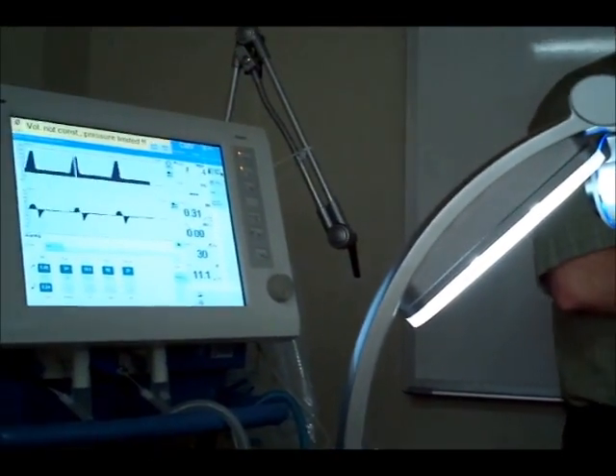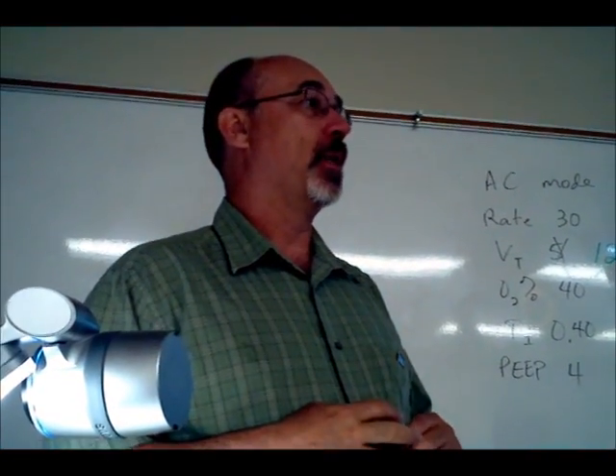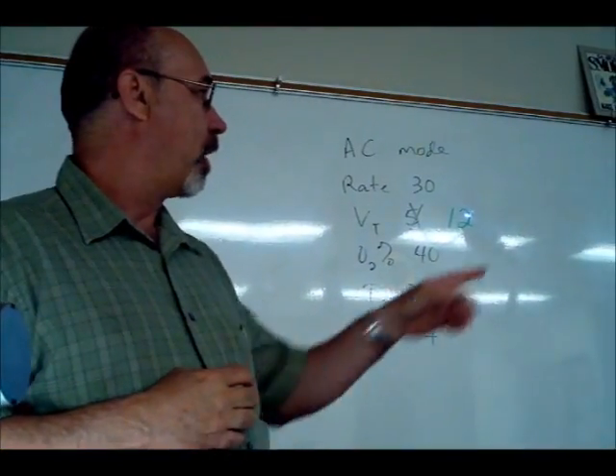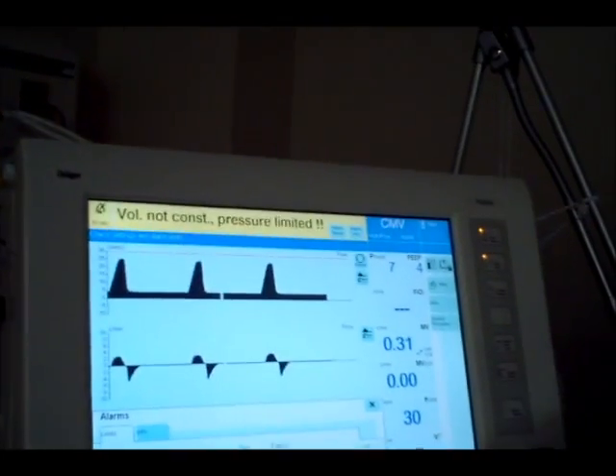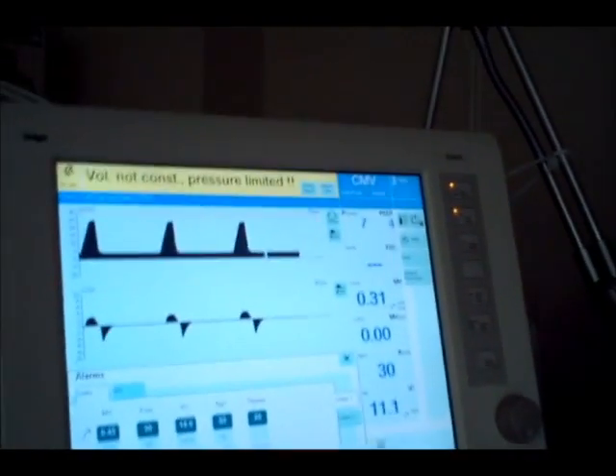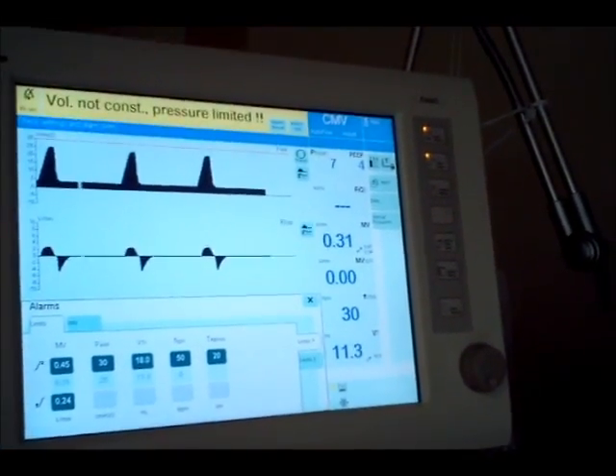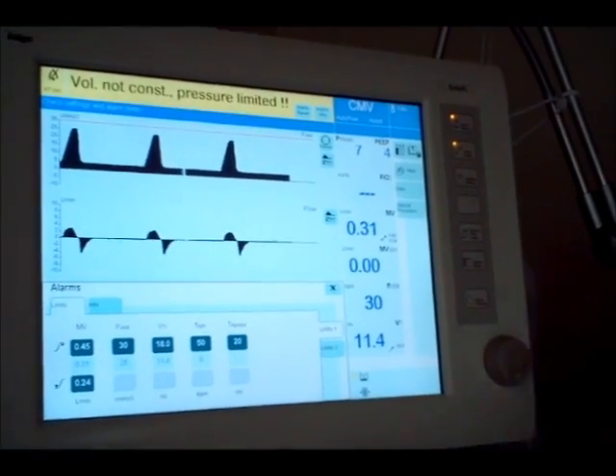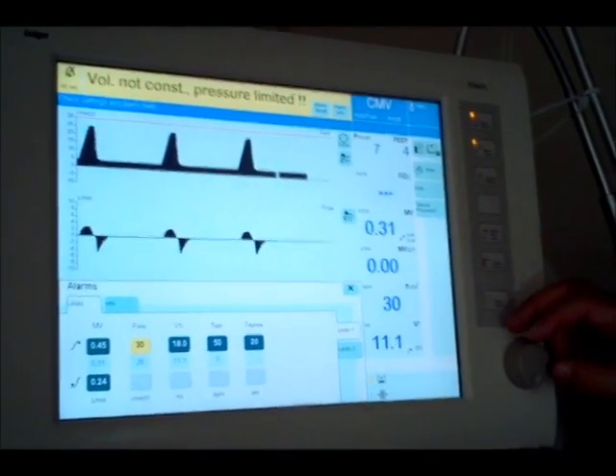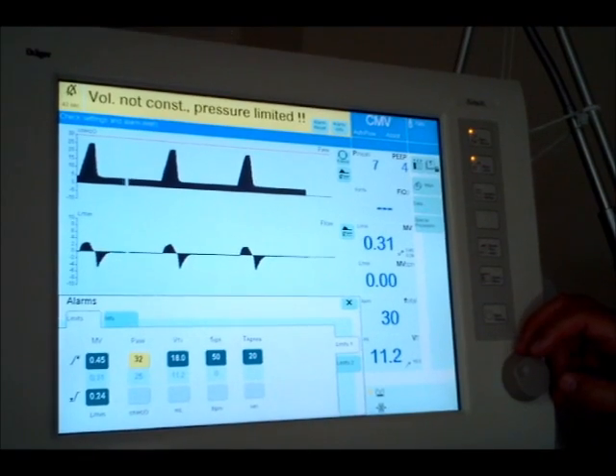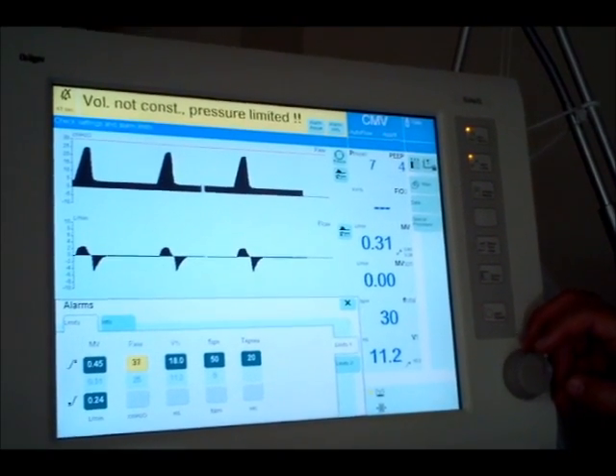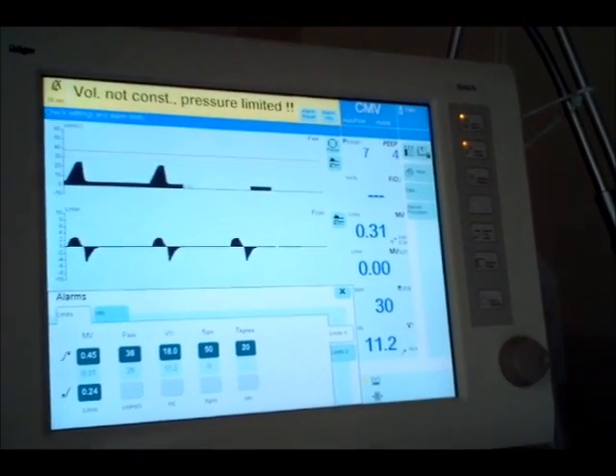We're getting a volume not constant, pressure limited alarm. Okay, so that's telling me that I'm not getting enough. My pressure limit is limiting my tidal volume that I'm supposed to be getting. The peak pressure is now limited to 25, so it's actually 5 below that number. So I need to come up on this a little bit. And I'm going to try 38. I'm not sure why I'm doing 38 right now.